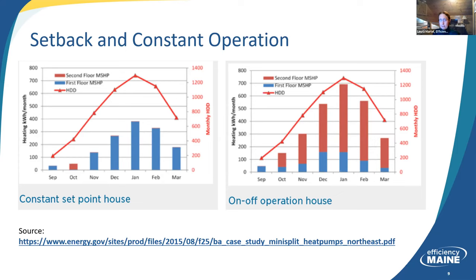On the right-hand side, they were turning off the heat pump at night and turning it back on in the morning. And what you'll see, not only does the second story heat pump have to contribute a lot more to the heating load of the home, but when you look at the sum of both heat pumps, you're looking at almost double the energy use by turning back the temperature at night and turning it back up in the morning.